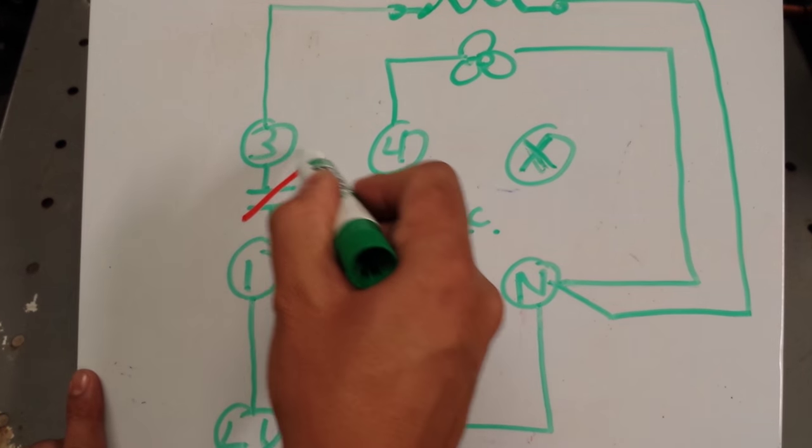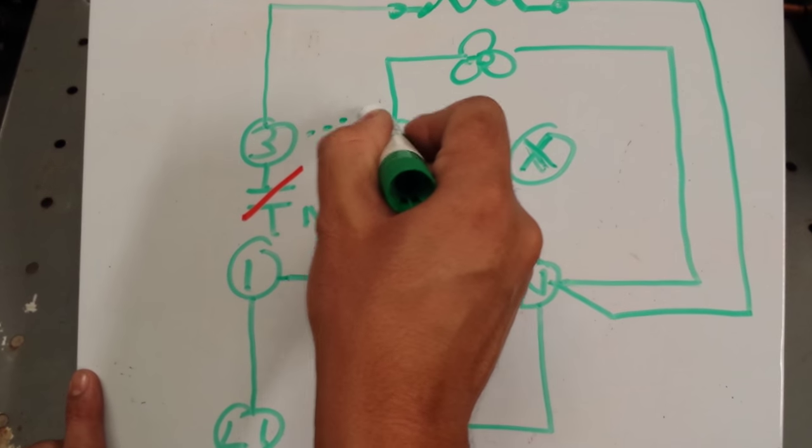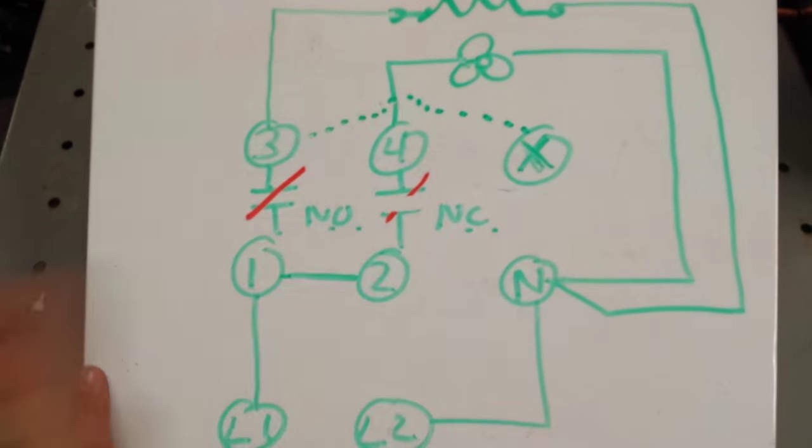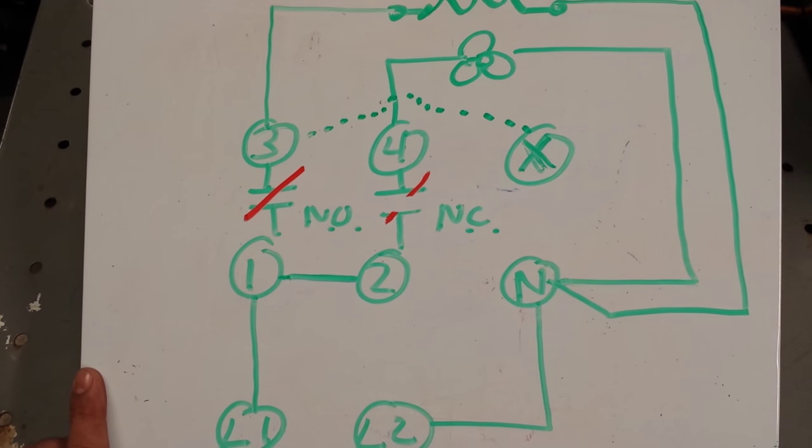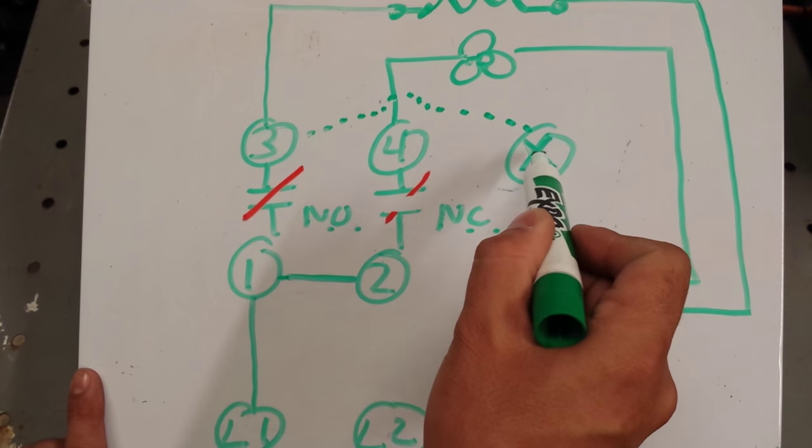Before we do that, let me tell you about the inside, behind the scenes wiring of that X terminal. So behind the scenes of the X, of the clock here, and I'll put this in dashes, you have a wire coming from terminal 3 to X. So what that means is L1 goes to 3, and then behind the scenes that L1 also feeds X.